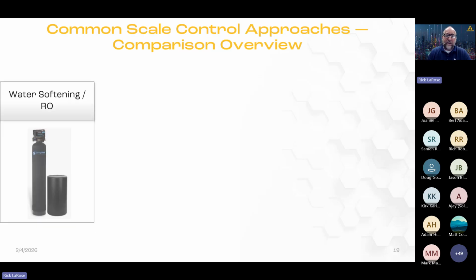The gold standard is basically water softening. Water softening, or in a boiler system, reverse osmosis if you really want to polish the water up. Both of those work by removing the hardness minerals from the water. When properly designed and maintained, these approaches are very effective at preventing scale and offering predictable performance.